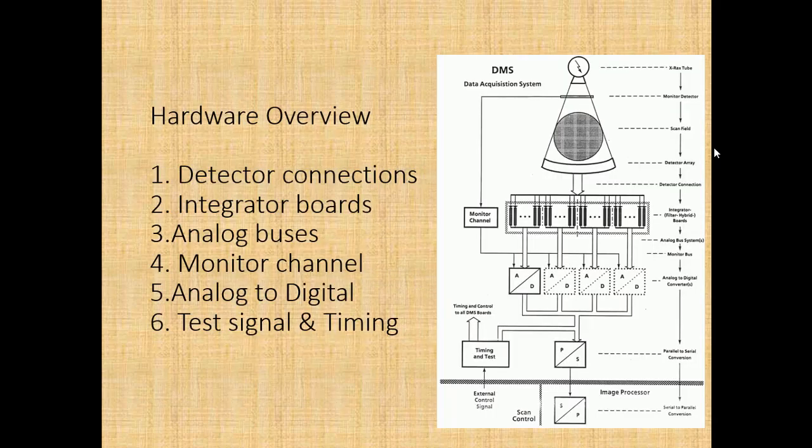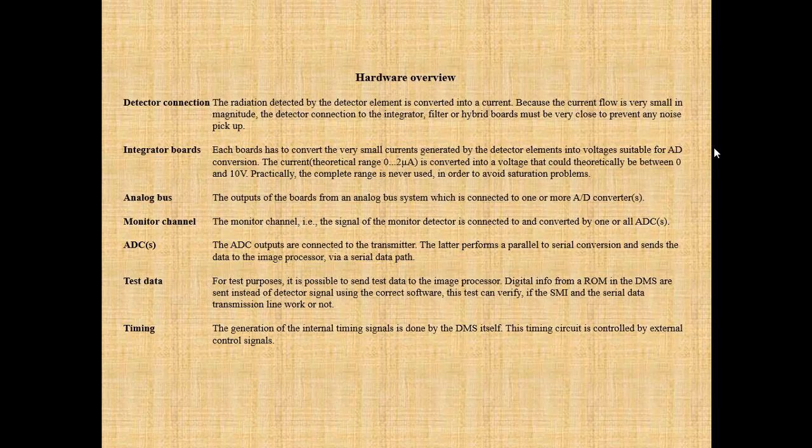Hardware overview covers: 1. detector connections, 2. integrator boards, 3. analog buses, 4. monitor channel, 5. analog-to-digital conversion, 6. test signal and timing. Regarding detector connections: the radiation detected is converted into a current. Because the current flow is very small, the detector connection to the integrator, filter, or hybrid boards must be very close to prevent any noise pickup.